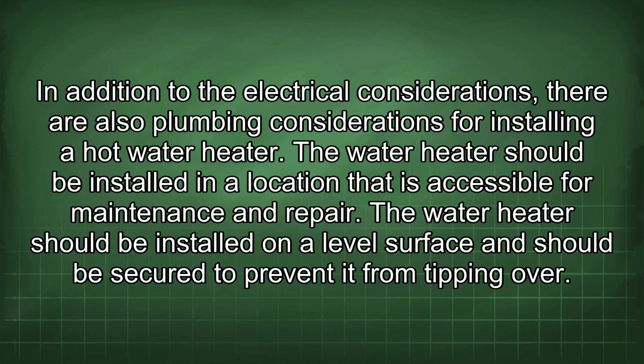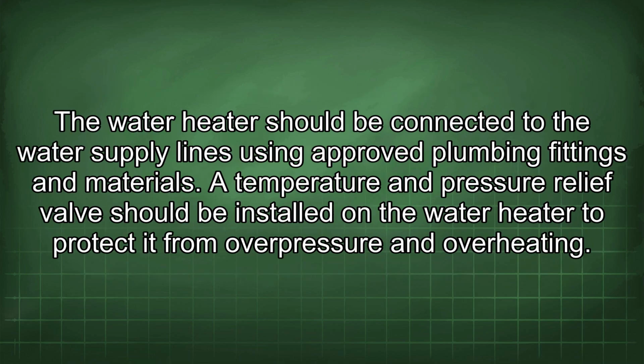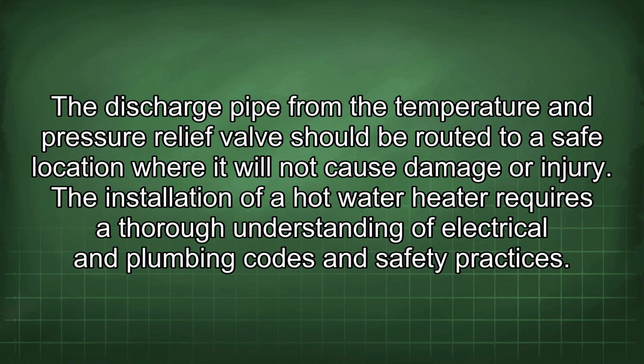In addition to the electrical considerations, there are also plumbing considerations for installing a hot water heater. The water heater should be installed in a location that is accessible for maintenance and repair. The water heater should be installed on a level surface and should be secured to prevent it from tipping over. The water heater should be connected to the water supply lines using approved plumbing fittings and materials. A temperature and pressure relief valve should be installed on the water heater to protect it from overpressure and overheating. The discharge pipe from the temperature and pressure relief valve should be routed to a safe location where it will not cause damage or injury.